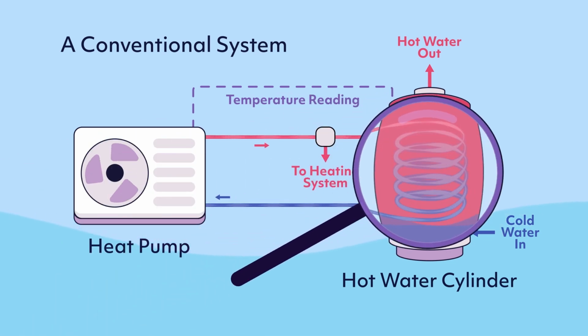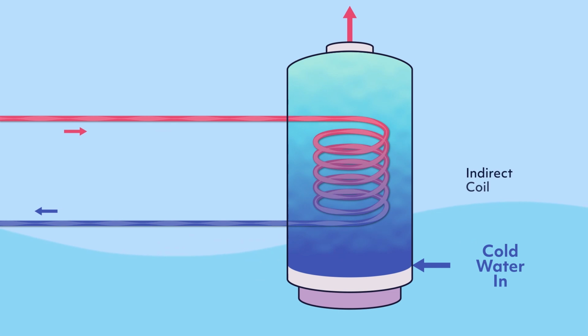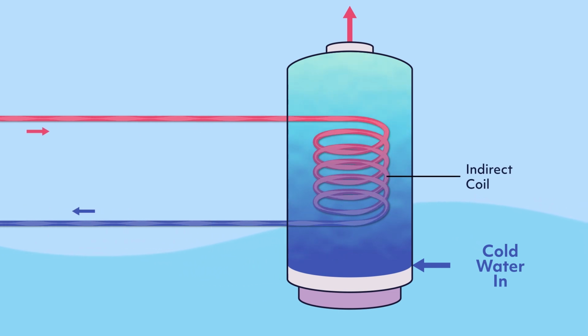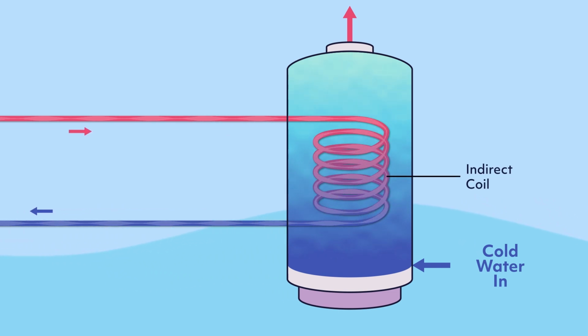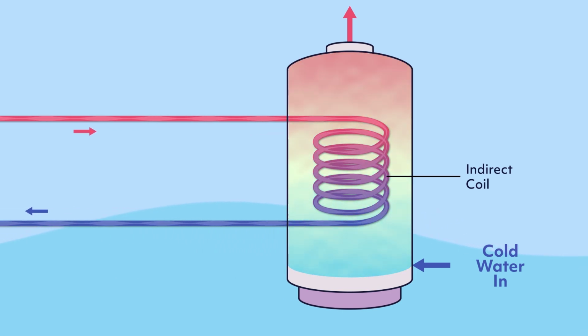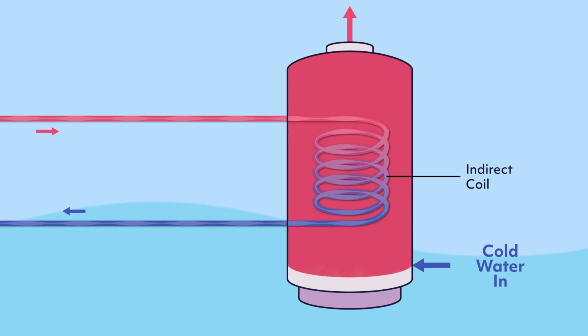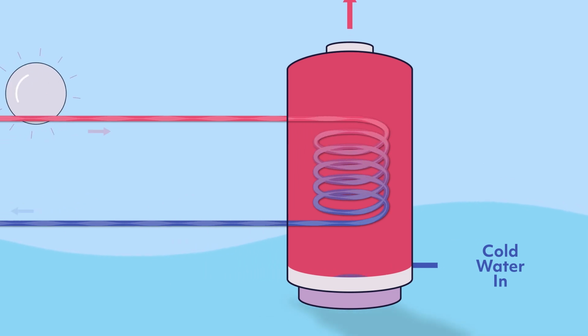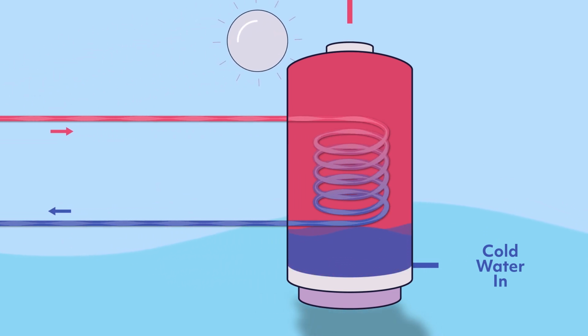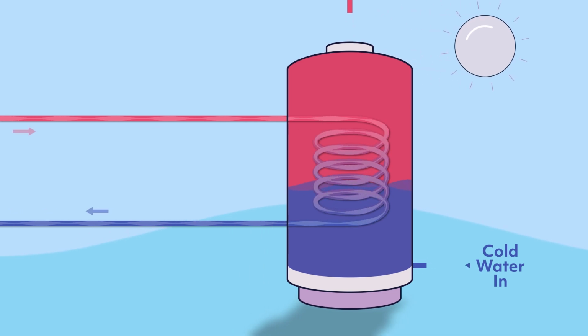For the system to work effectively, the hot water cylinder needs a very large coil to get as much surface area as possible between the coil and water stored inside. This is so the thermal energy can travel easily, with little resistance, keeping the temperature of the system loop as low as possible. When the system loop temperature is low, the efficiency, or COP, of the heat pump is at its best. Households usually use about half of the capacity of a hot water cylinder each day.